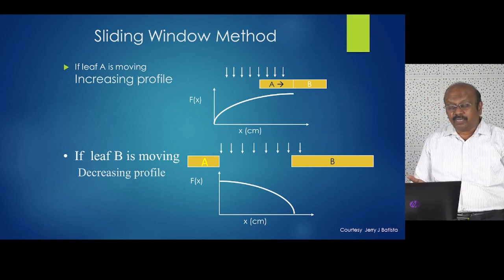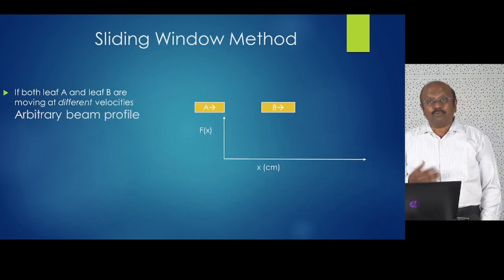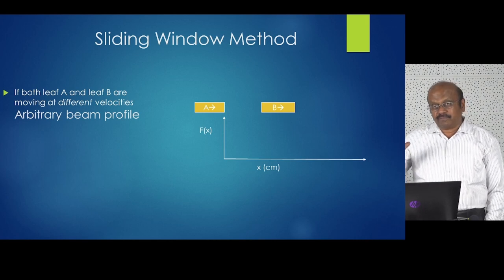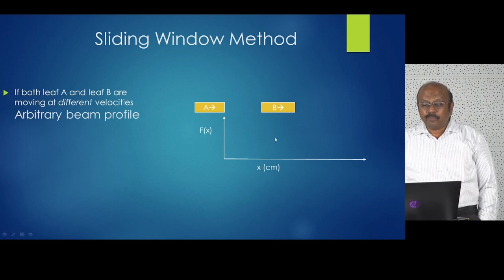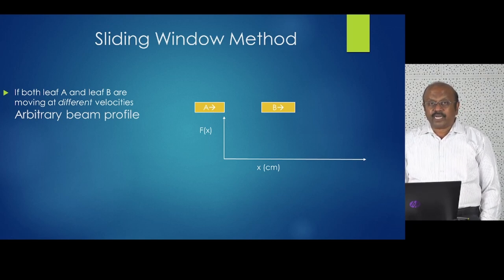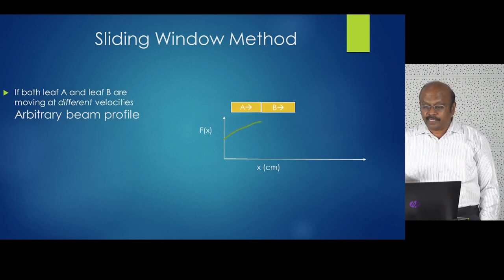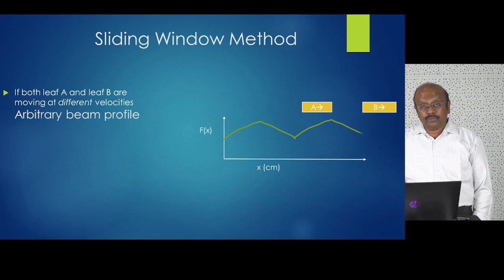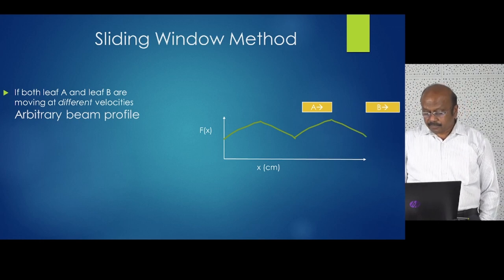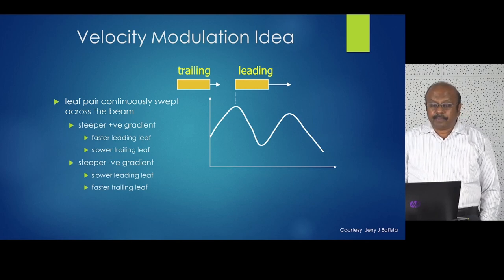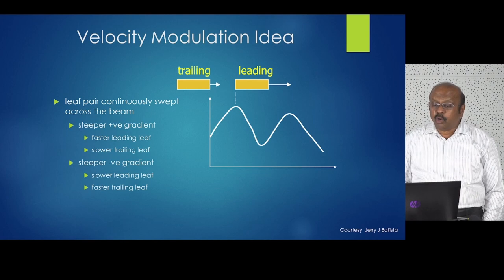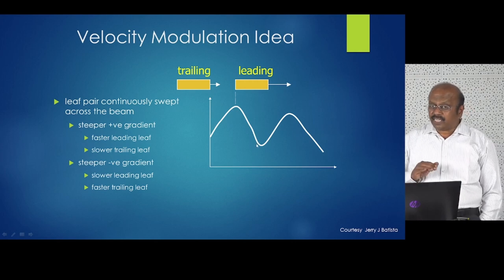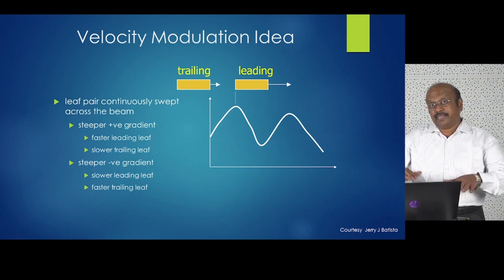The steepness of the profile can be changed by changing the velocity of the leaf. For an arbitrary profile with valleys and hills, you use two leaves: a leading leaf and a trailing leaf. The trailing leaf moves to produce an increasing profile, and the leading leaf moves to produce a decreasing profile. You can make any arbitrary profile: for a steeper positive gradient, use a faster leading leaf and slower trailing leaf; for a steep negative gradient, use a slower leading leaf and faster trailing leaf.